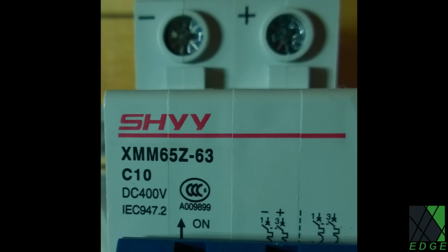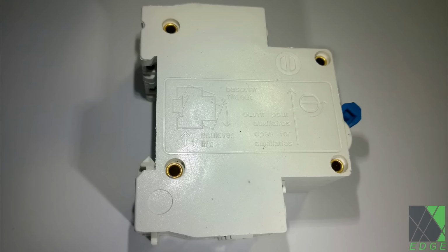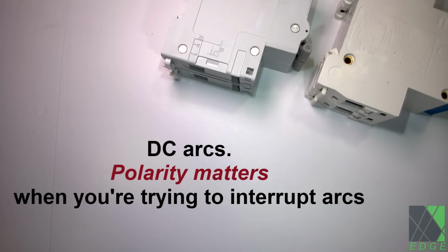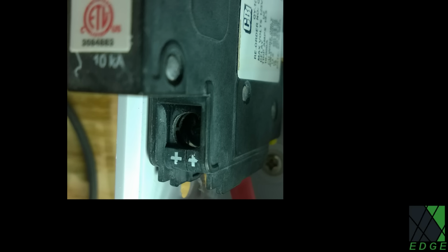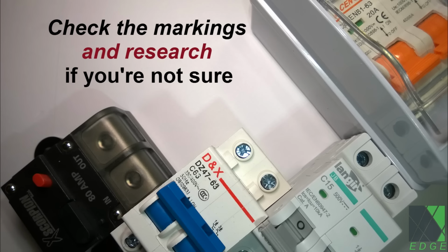It can be rather confusing to understand, but think of it this way: the polarized circuit breaker must interrupt the DC arc on disconnect or trip, and in order to do that, the voltage must be flowing in the correct direction. Markings on breakers can be confusing and vary amongst manufacturers. If you see positive and negative markings on the breaker, slow down and take the time to examine the specifications and installation instructions. Otherwise, this type of circuit breaker can be dangerous and won't protect your installation.